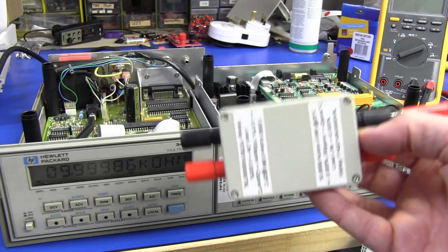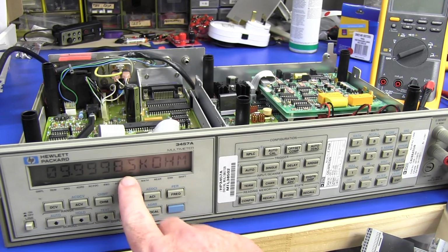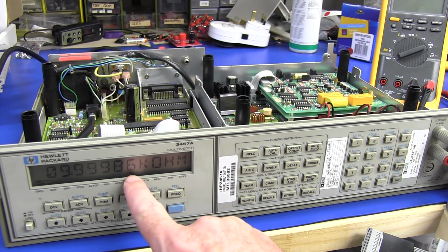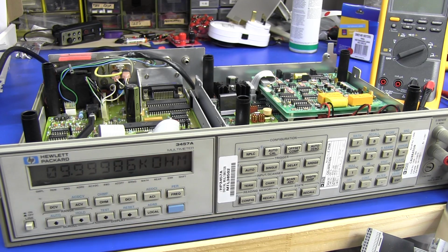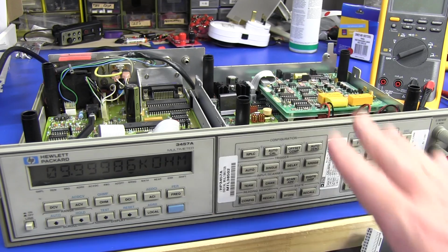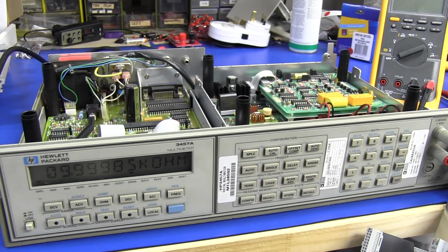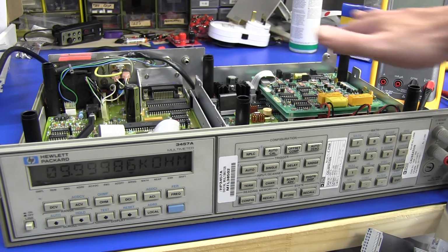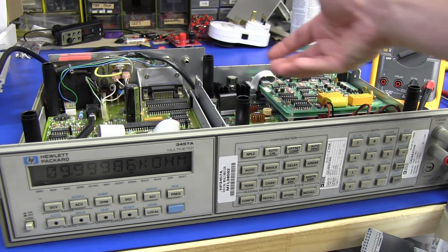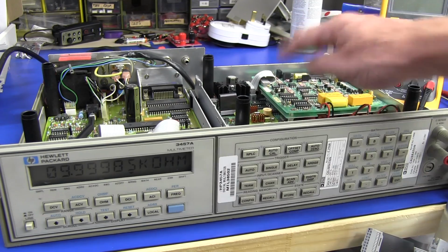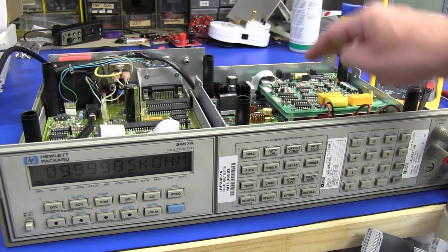Alright, what I've got here is my resistance standard hooked up to this thing. It's close enough to 10k here. So this least significant digit here represents 1 ppm of that 10k, so 1 part per million. And this thing's tempco is incredibly low, in the order of parts per million. So any change in temperature in here can generate small EMF effects, or thermocouple effects in the joints, or a temperature gradient across components that can affect the reading when you're talking down in this region.